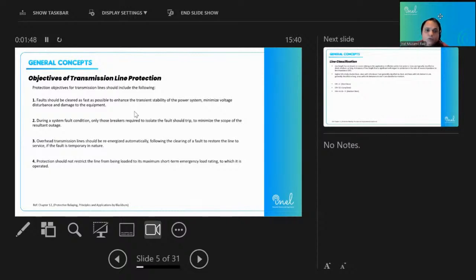First of all, we can't stop the faults. We can only protect the connected equipment. So if there is a fault, we need to open only those breakers which are mainly affected. This property is the selectivity of the protection system; it must be selective in nature. In other words, if there is a fault between points A and B, then the outage should be only in the region between A and B, not on the side of C or D. It should know where the fault is actually happening and what portion of the network it needs to protect and keep de-energized.